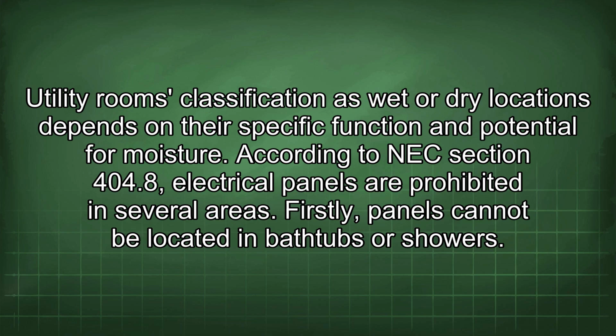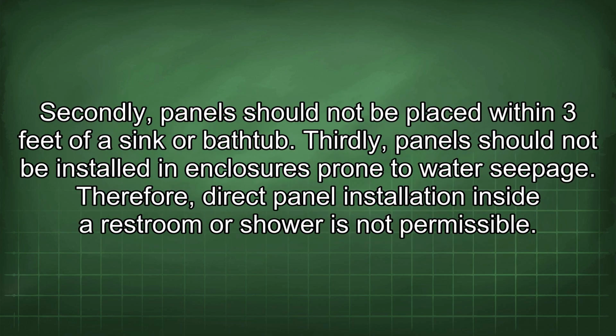According to NEC Section 404.8, electrical panels are prohibited in several areas. Firstly, panels cannot be located in bathtubs or showers. Secondly, panels should not be placed within 3 feet of a sink or bathtub. Thirdly, panels should not be installed in enclosures prone to water seepage. Therefore, direct panel installation inside a restroom or shower is not permissible.